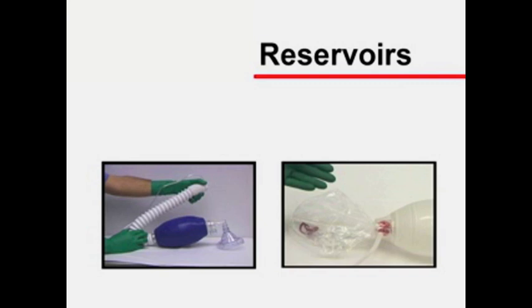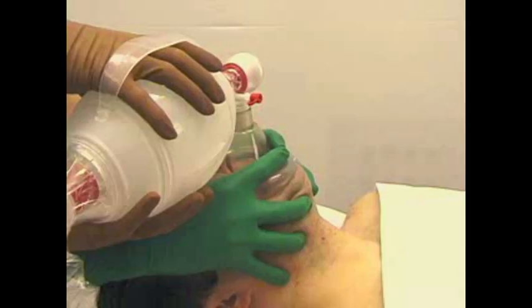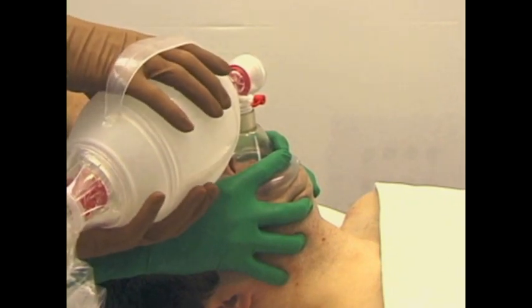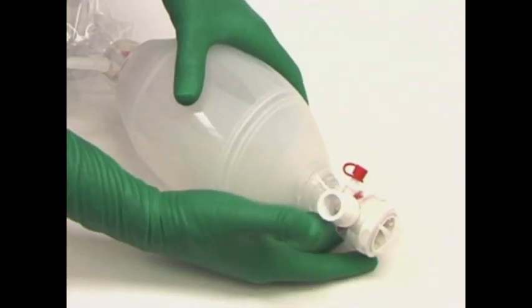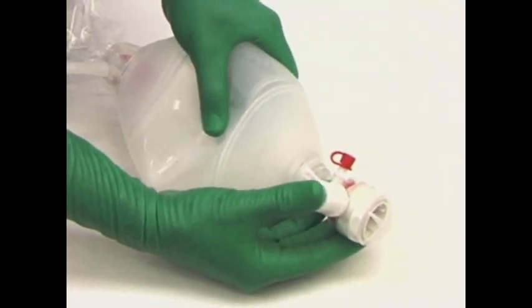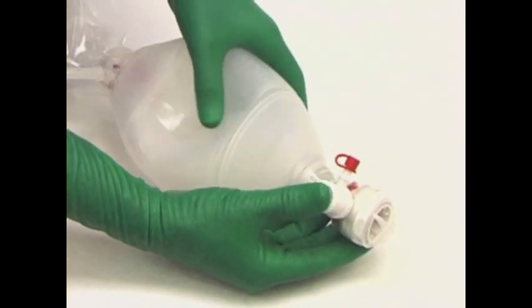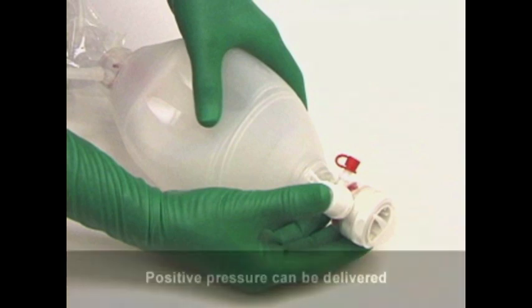The purpose of these reservoirs is to maximize the delivered oxygen concentration. A bag valve device's capability for delivering positive pressure ventilation should be tested before use. This can be achieved by sealing the bag valve device connector with the thumb and squeezing the bag with reasonable force. If it is difficult to compress the bag or if air is forced between the connector and the thumb, positive pressure can be delivered.